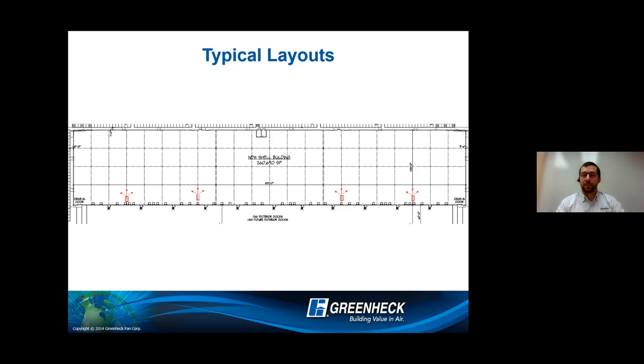When we do that, we just throw it at low velocity and let it hang there. All that heat rises right up to the ceiling with this type of equipment, regardless of how much air you try to circulate with the units. It tends to rise towards the ceiling. So the key is really driving it down to the floor with the velocity out of the diffuser, or combining it with HVLS fans to circulate the air within the space.